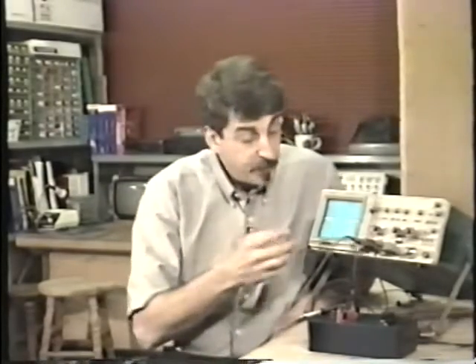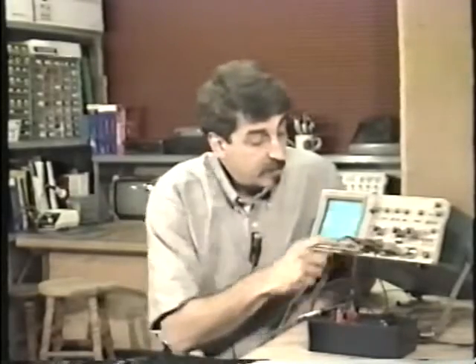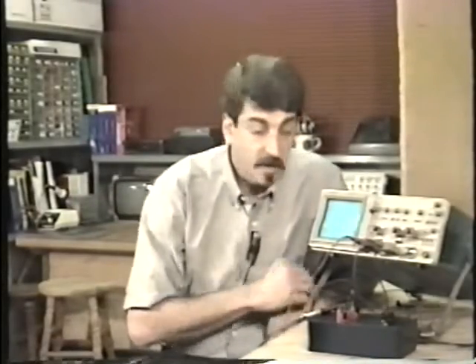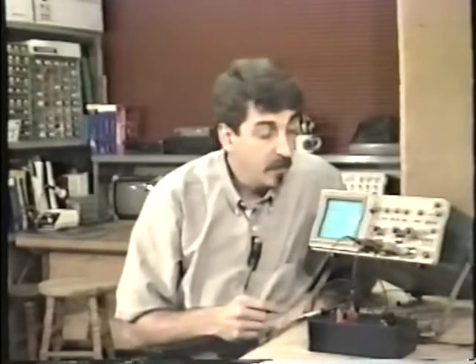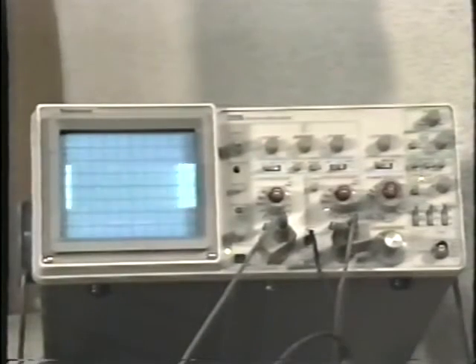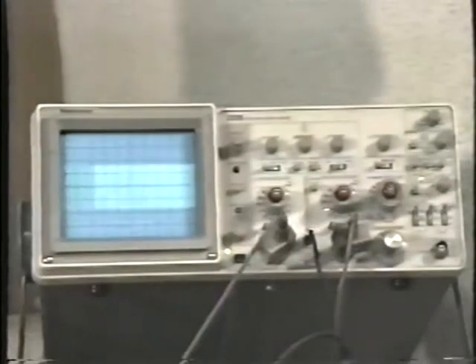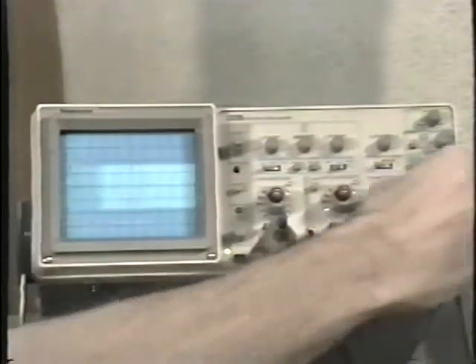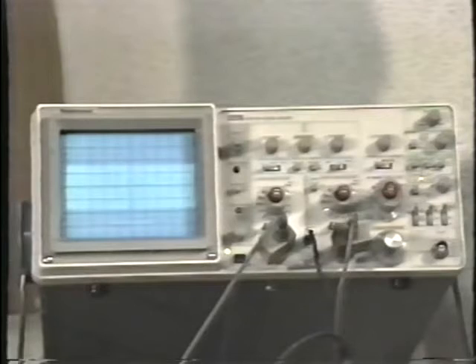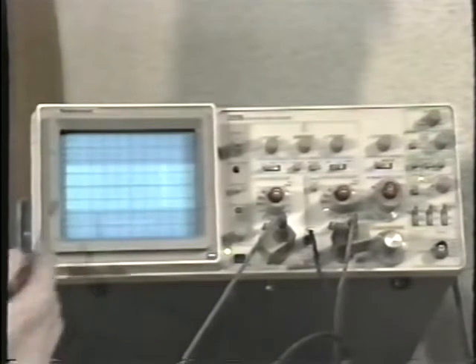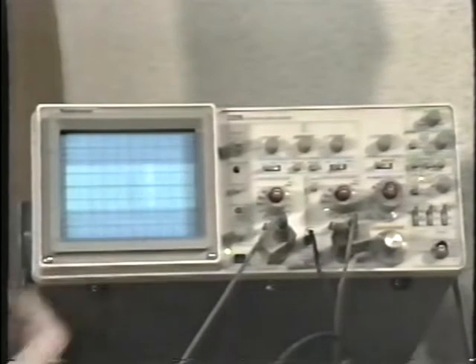Well, it's starting to move so fast now that we can speed it up more, and it's not going to look like much. So let's take a look at a signal now, and this is the signal coming out of my little test box that I have down here. Let's speed up the horizontal sweep and see if we can make some sense of what we have on the screen. There's 2 milliseconds per division. 1 millisecond per division, that's 1/1000th of a second for the beam to move across each horizontal division across the face of the graticule.